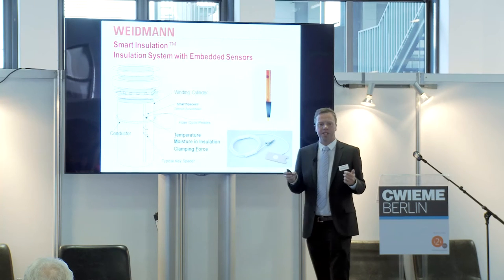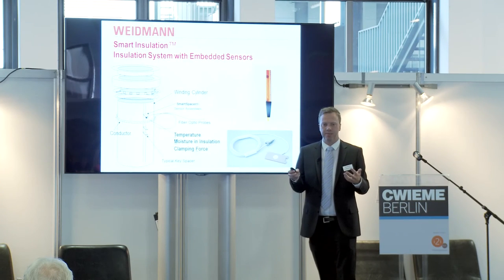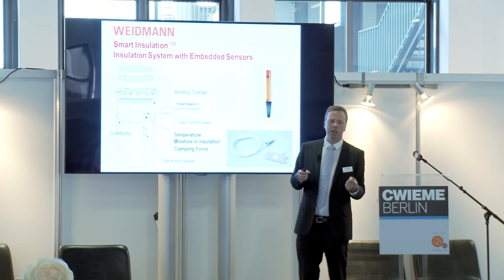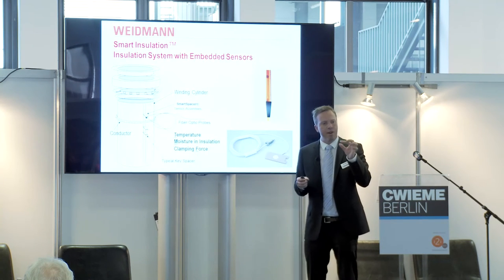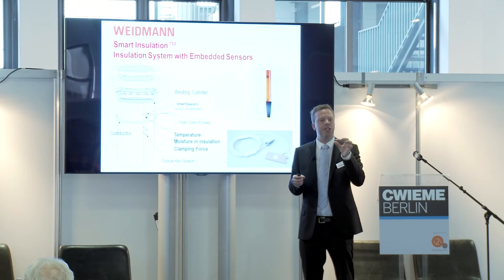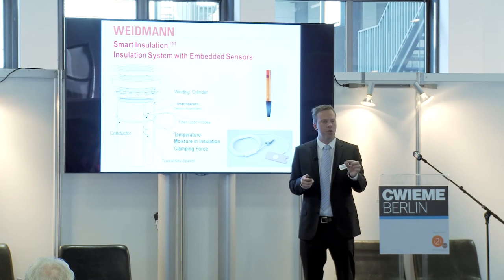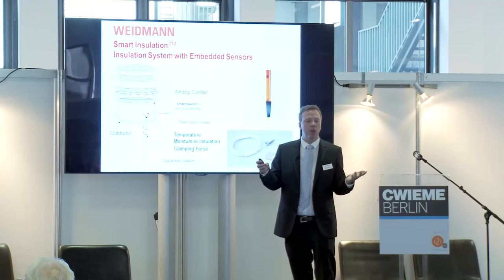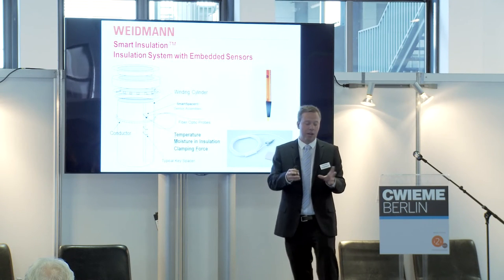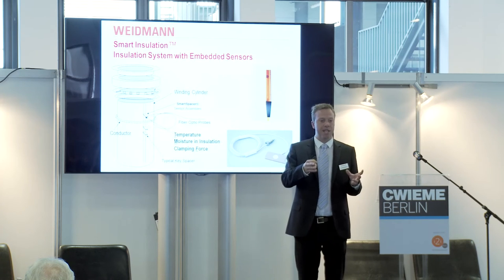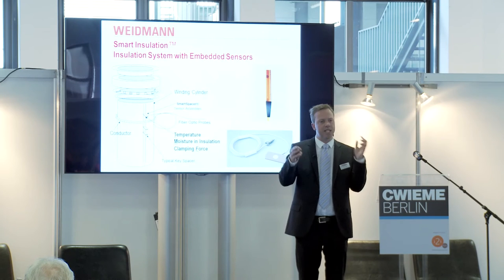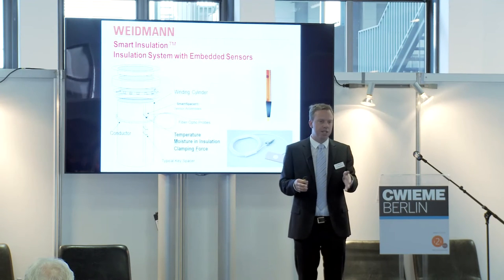Secondly, and this is where it starts to get interesting and unique, Weidmann are currently working on developing a fiber-based sensor in the insulation that can actually capture the moisture content of the solid insulation. So this would be a world first. Today we use a calculation to look at the potential content, which is very inaccurate because of the way it's calculated using a consistent temperature.